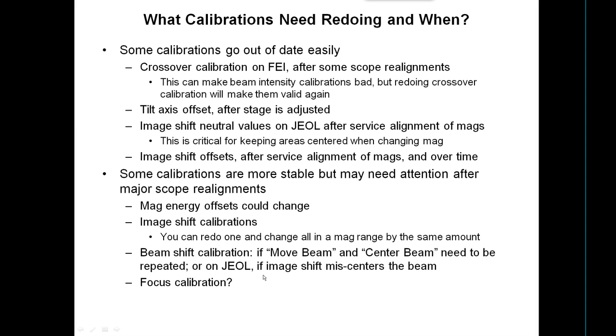Some calibrations are more stable but may need attention after major realignments. Mag energy offsets could change, though we haven't really seen that happen — it's still good practice after a major realignment. Image shift calibrations could change on FEI machines because there's an alignment that calibrates the relationship between image shift coils and the amount of image shift movement. But this is global, so you just redo them at one mag and are given the option to shift all calibrations by the same amount, then save them out.